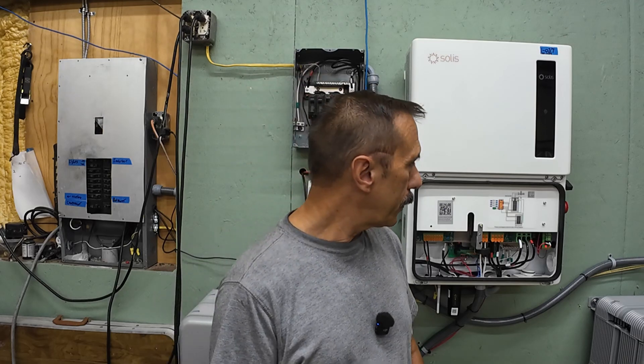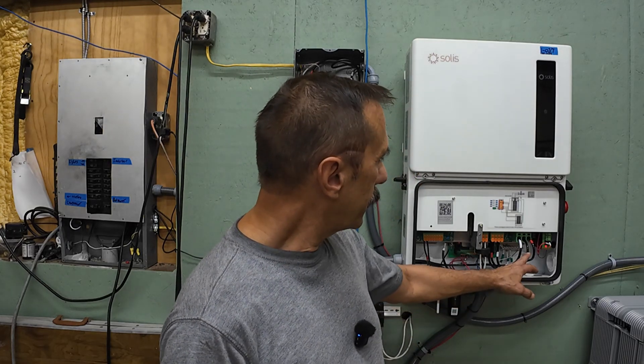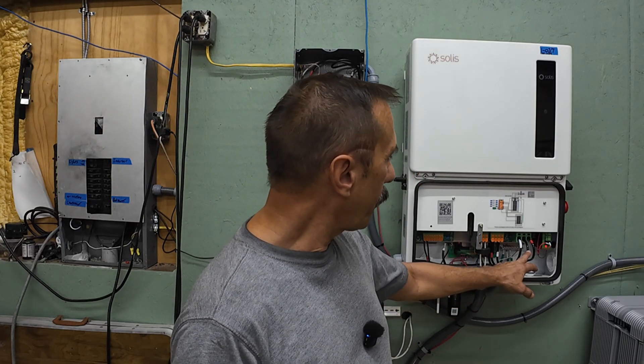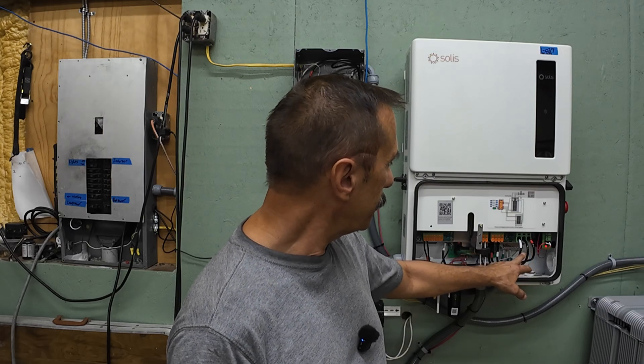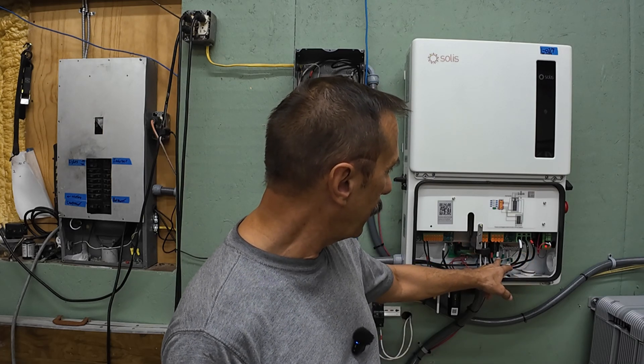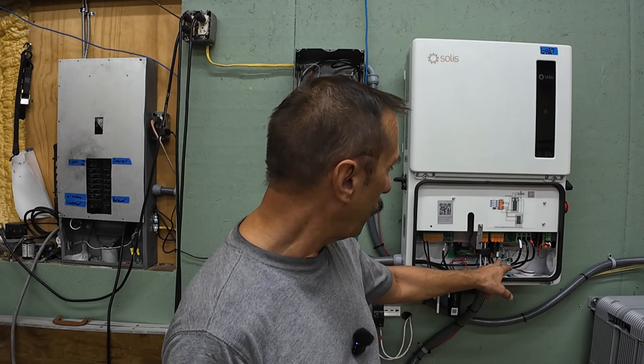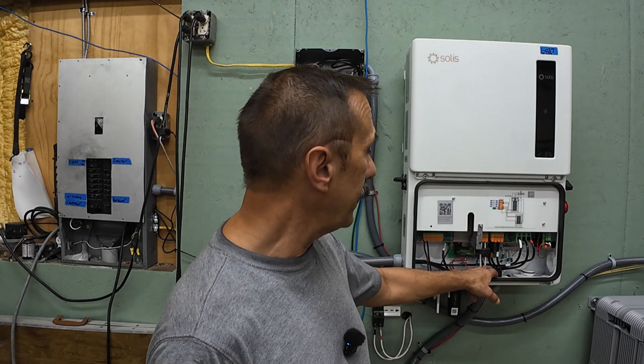You want to size your wires properly. Now, in this inverter, you can use up to four-gauge on the grid connections and six on the backup port. Being a high-voltage system, the battery, you only need six-gauge wires also. That's what makes a high-voltage system so awesome. It's very easy to wire up.